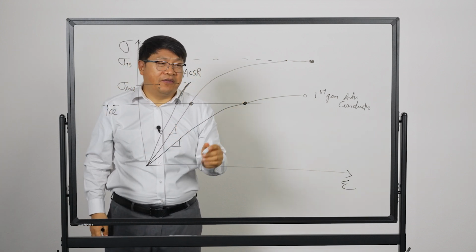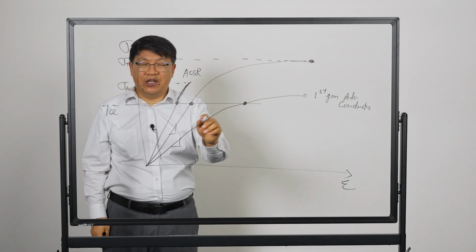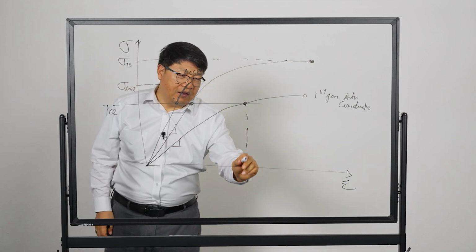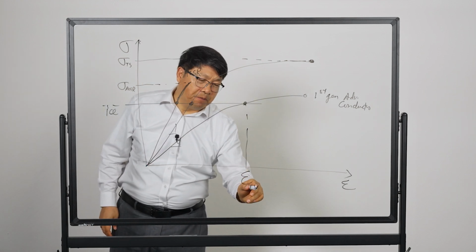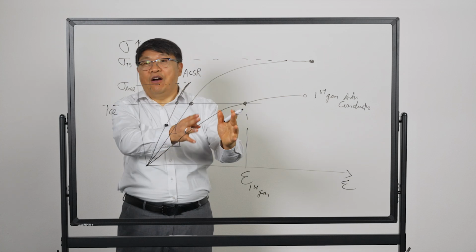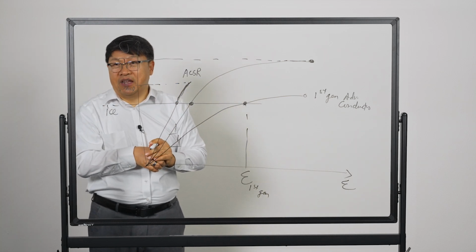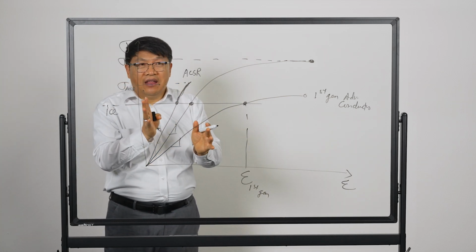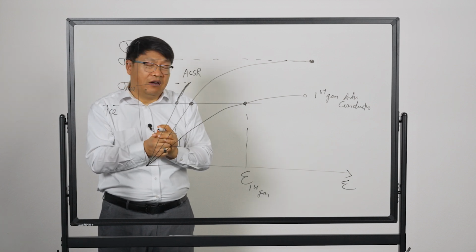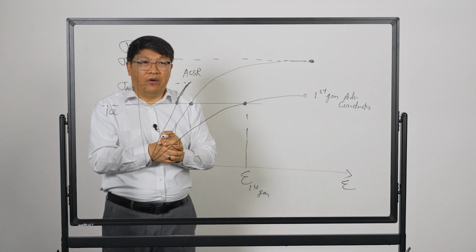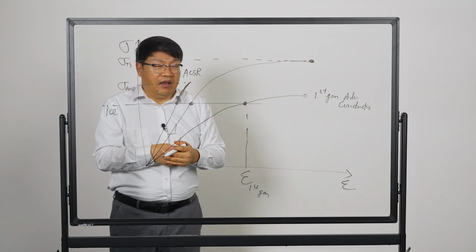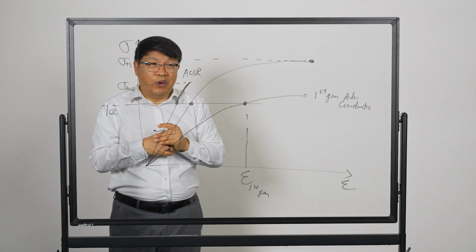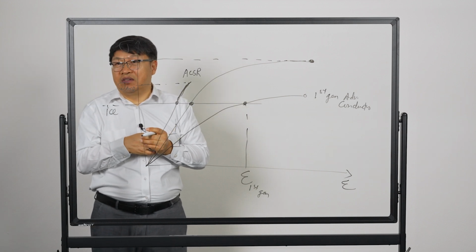But if you look at the first generation conductor, because of the low modulus in the core, they will have significantly more sag. And that often limits the applications. This is why the first generation advanced conductors are just not adequate for very long span applications, heavy ice regions, and also if you have a lot of wind, the blowout might be a concern as well.